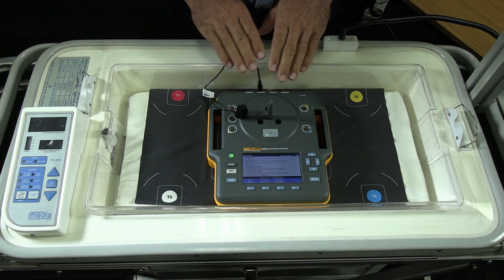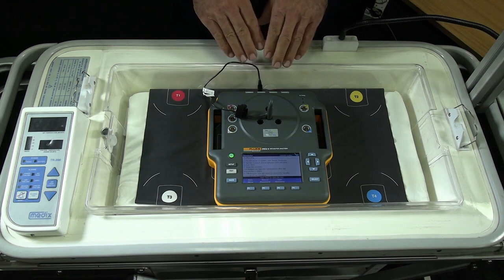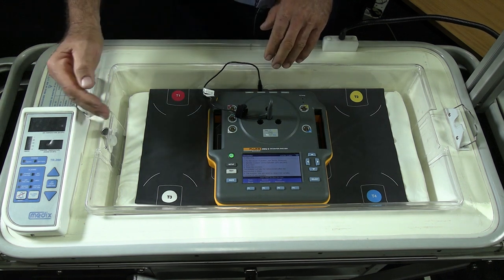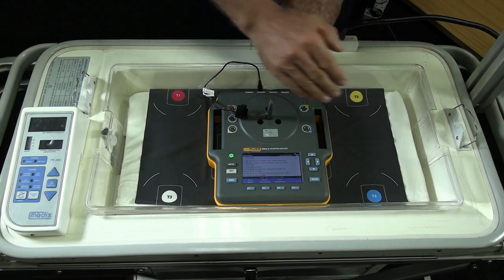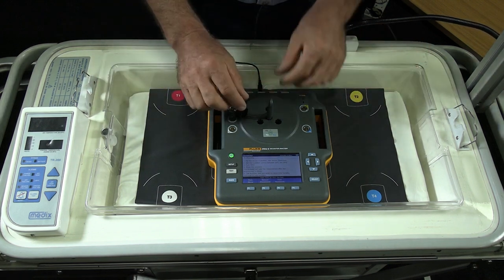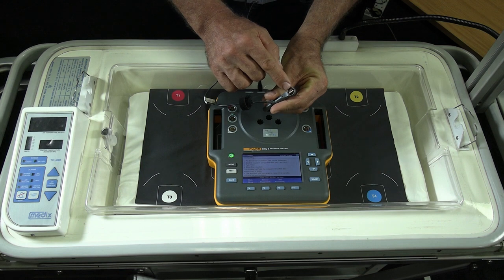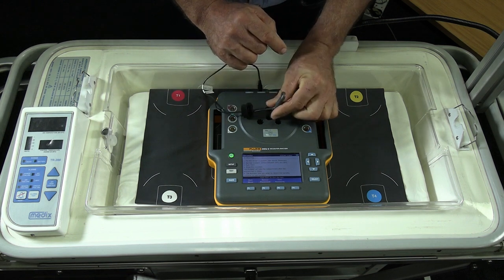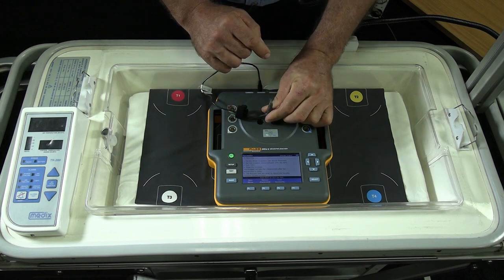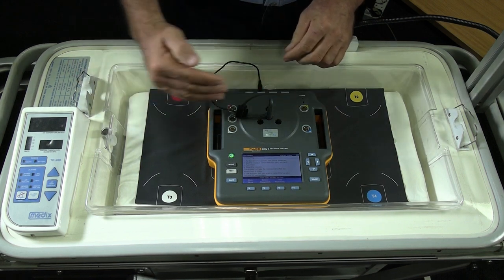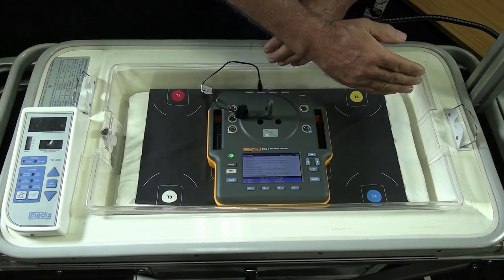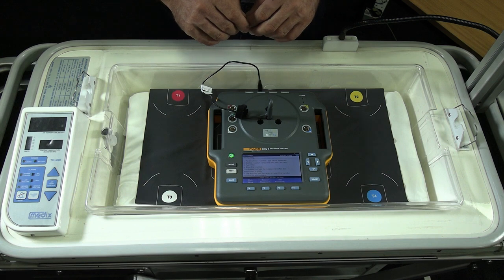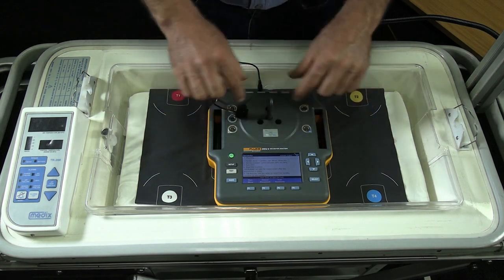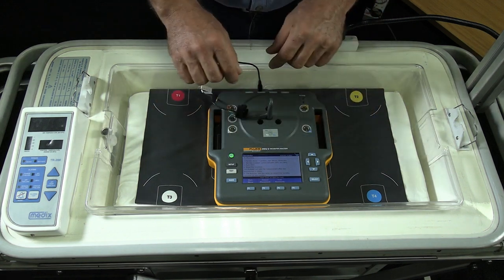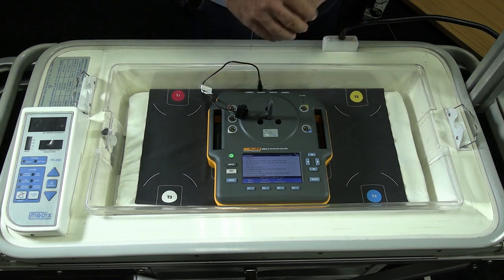Now, two important things with the airflow sensor. Firstly, we've got to make sure what the direction of airflow across the unit is, so that we turn the receiving area of the unit into that same direction, so the air will flow past our sensor. And the second thing is to make sure you've removed all the other sensors, because you do not want anything that causes turbulence around the airflow sensor.